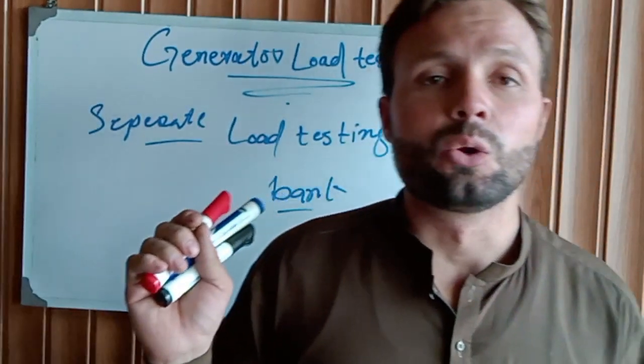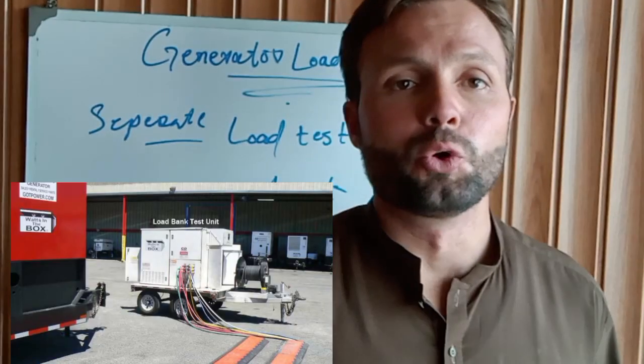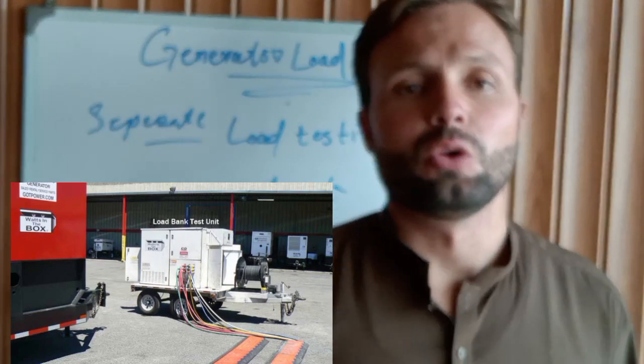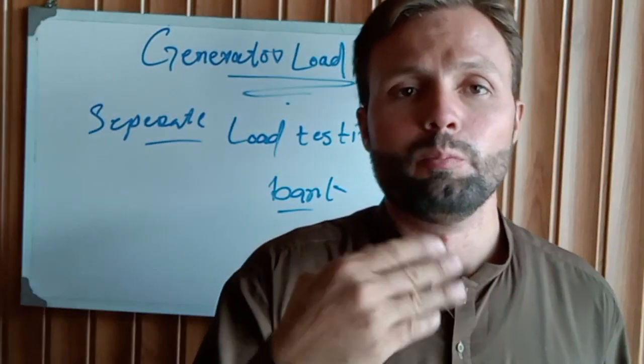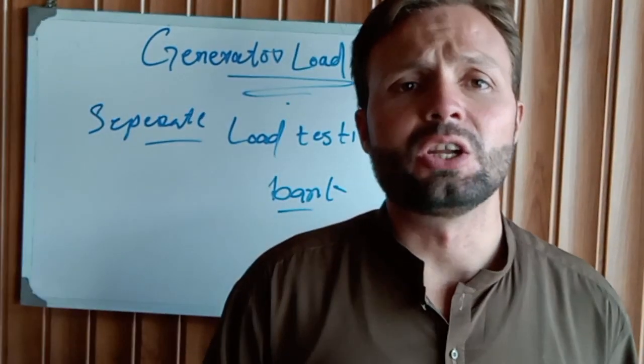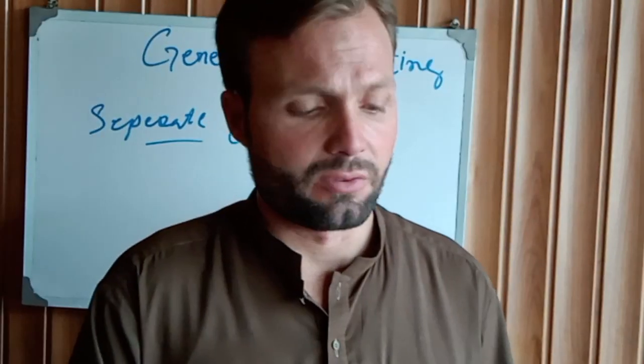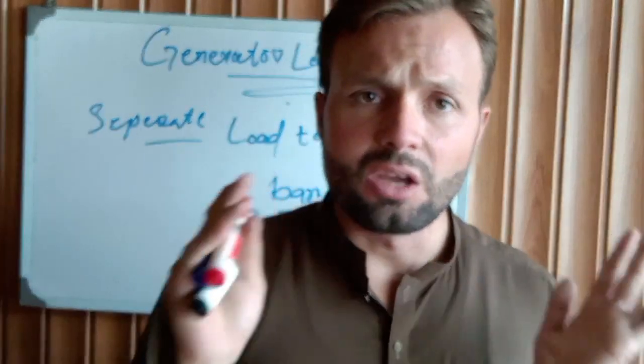The main and basic procedure of generator testing is: take the generator load bank, put it on the 15 kilowatt generator with a maximum 13 kilowatt load, and then check the generator behavior — check the sound, the emissions, the temperature, the engine oil pressure. You can check everything by putting load on the generator.